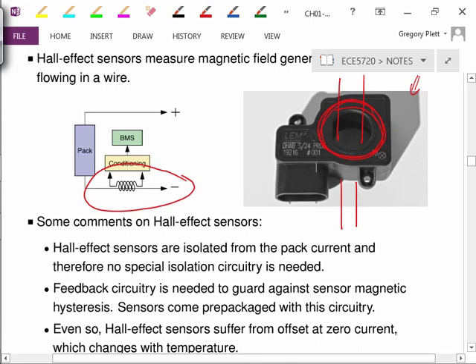However, it's a magnetic device, and magnetic devices have hysteresis—if I follow one pathway and get one set of measurements, reversing the pathway won't just reverse the measurements, it'll give a different set entirely. This can add an offset or bias to the measured current, which wreaks havoc with some of the algorithms we'll talk about. So we have to calibrate that offset out somehow, whether electronically or in software.